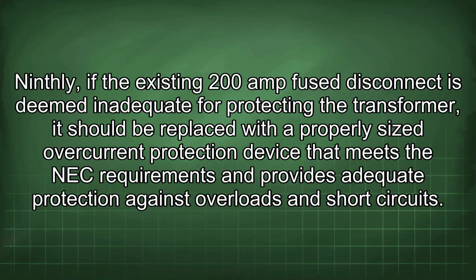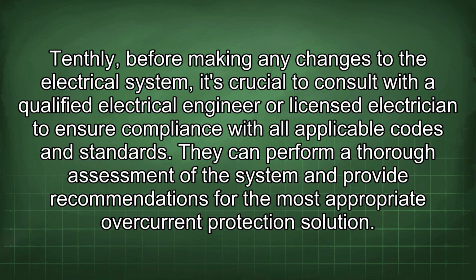Ninthly, if the existing 200 amp fused disconnect is deemed inadequate for protecting the transformer, it should be replaced with a properly sized overcurrent protection device that meets the NEC requirements and provides adequate protection against overloads and short circuits. Tenthly, before making any changes to the electrical system, it's crucial to consult with a qualified electrical engineer or licensed electrician to ensure compliance with all applicable codes and standards. They can perform a thorough assessment of the system and provide recommendations for the most appropriate overcurrent protection solution.